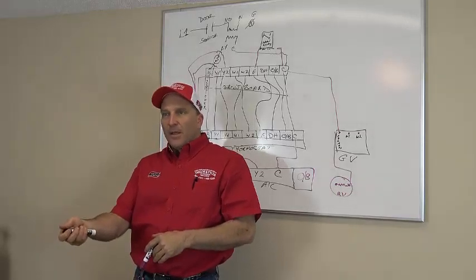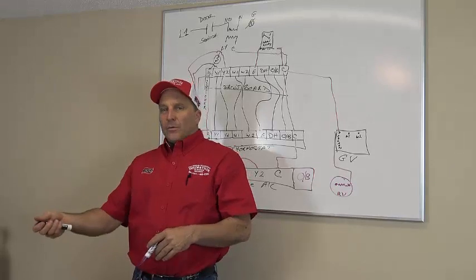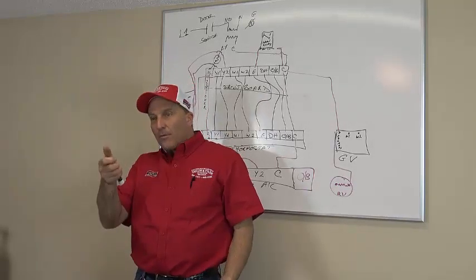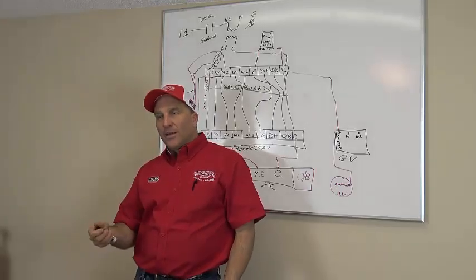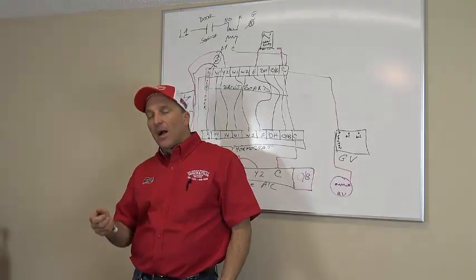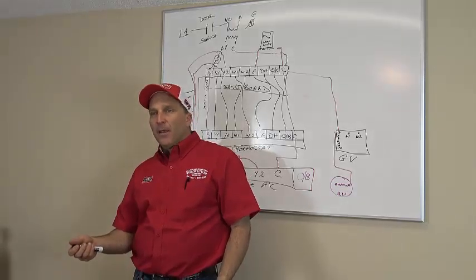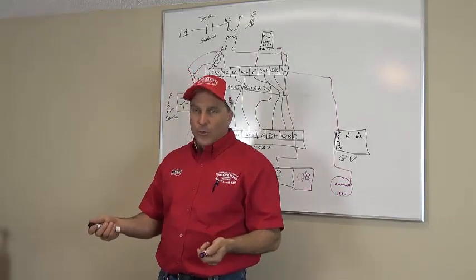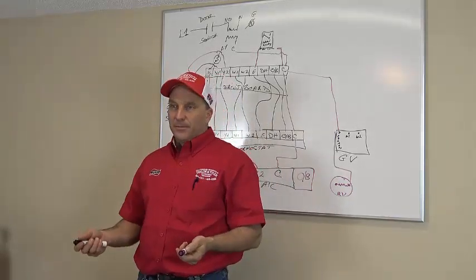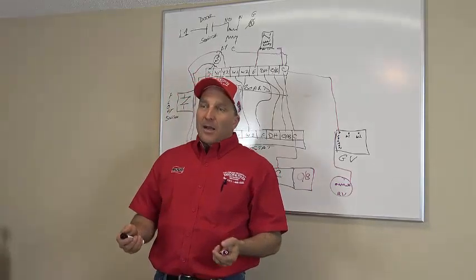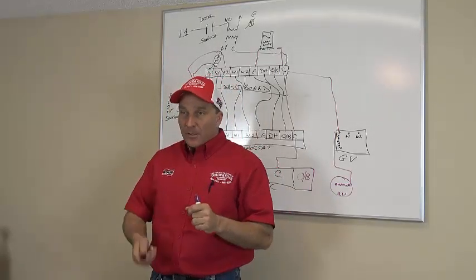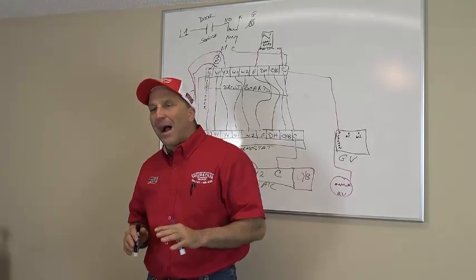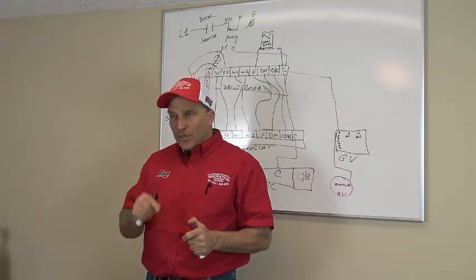Remember that. If you go from ground to 24 volts, are you finding all the problems? You may or may not be, depending upon if your common is grounded. If you go common to R and you don't read anything, but you go ground to R and you read 24 volts, you don't have a common. You've got a bad common. A lot of times on a regular light switch, if you're reading 70 volts, your problem is not your power. Your problem is your common.